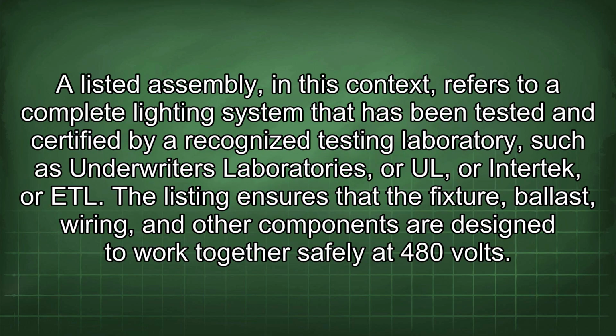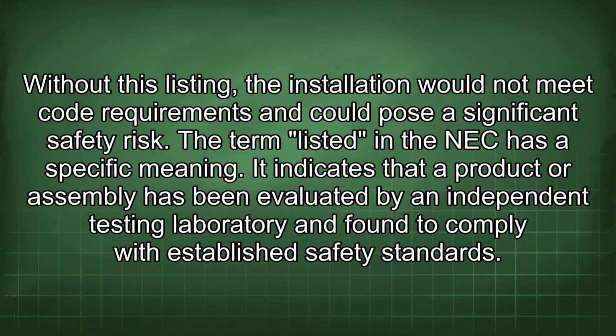A listed assembly, in this context, refers to a complete lighting system that has been tested and certified by a recognized testing laboratory such as Underwriters Laboratories, or UL, or Intertek, or ETL. The listing ensures that the fixture, ballast, wiring, and other components are designed to work together safely at 480 volts. Without this listing, the installation would not meet code requirements and could pose a significant safety risk.